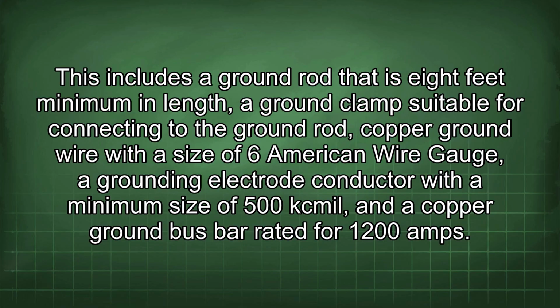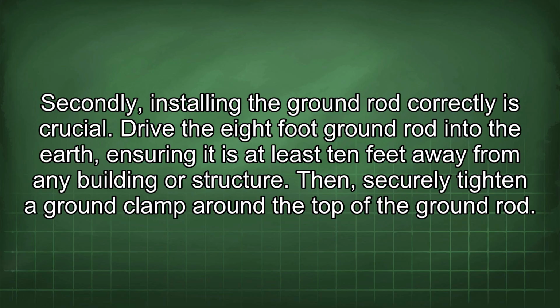ground rod, copper ground wire with a size of 6 American wire gauge, a grounding electrode conductor with a minimum size of 500 kcmil, and a copper ground bus bar rated for 1200 amps. Secondly, installing the ground rod correctly is crucial. Drive the 8-foot ground rod into the earth, ensuring it is at least 10 feet away from any building or structure. Then, securely tighten a ground clamp around the top of the ground rod.